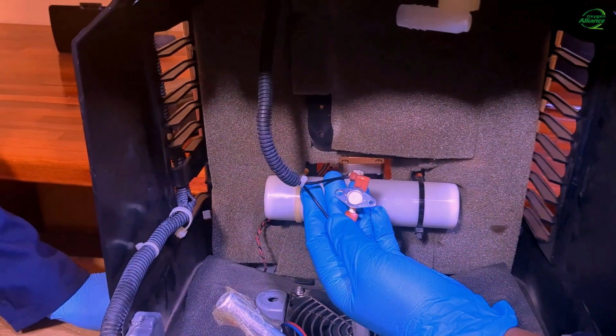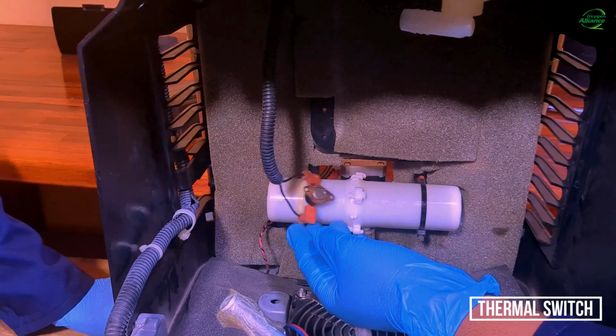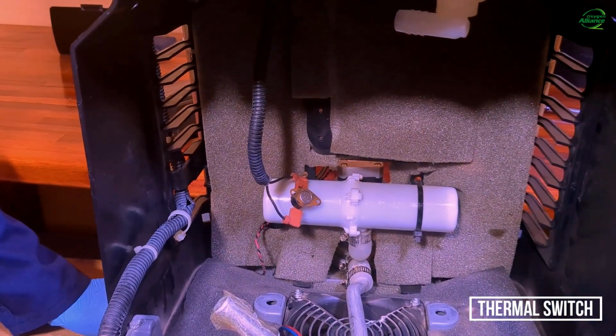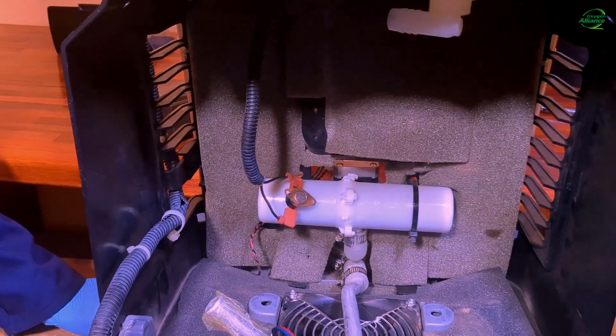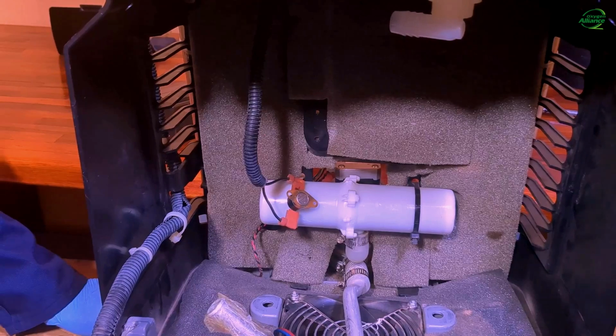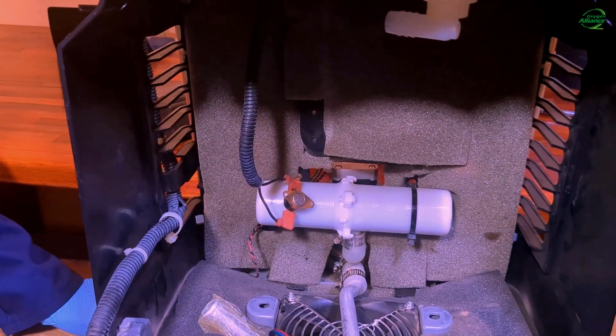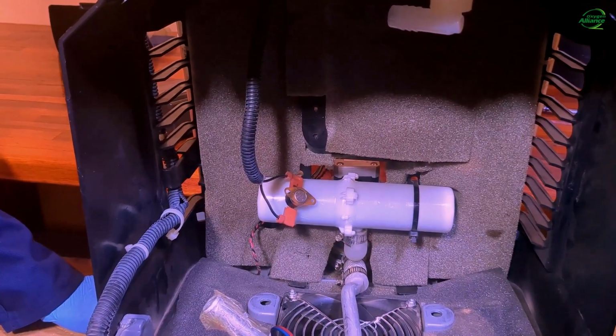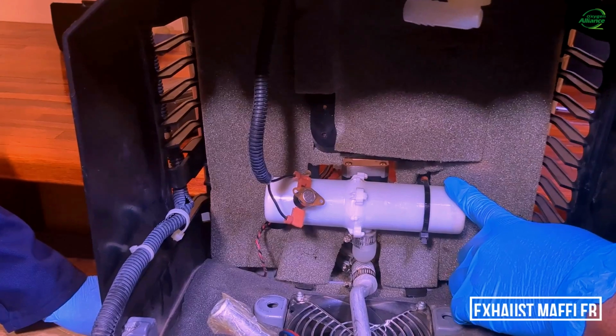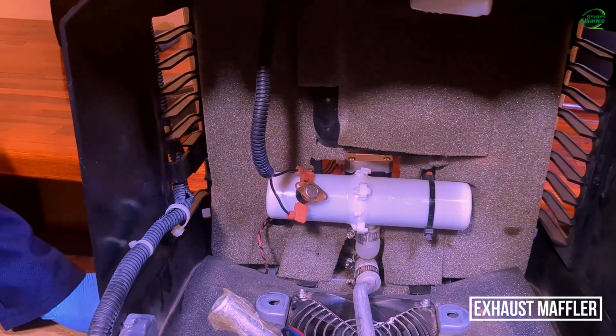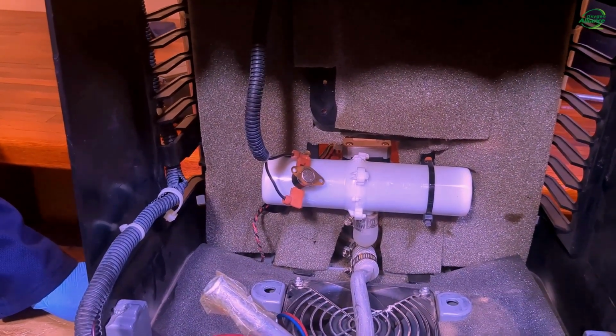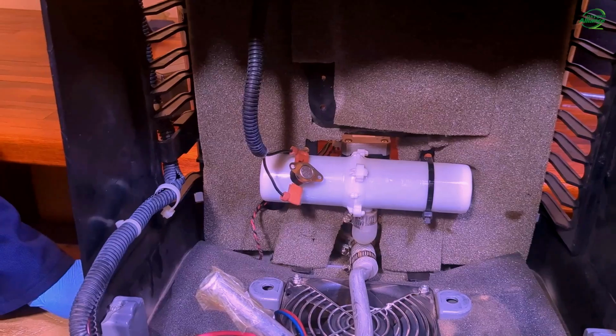So down here we also have the thermal switch, which is used to protect the compressor. It senses the temperature at which it is operating, and if it is too high, it cuts off power to the compressor. And lastly, we have the outlet muffler. This is there to reduce the noise that nitrogen may make as it is being exhausted to the environment.